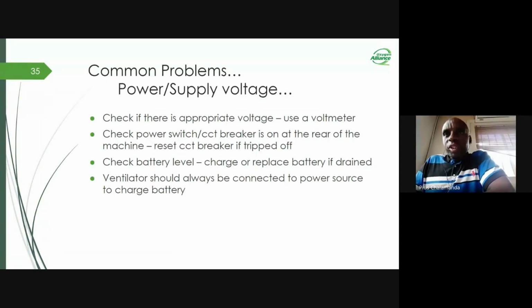You can also check the power switch at the back of the machine, or a circuit breaker at the back of the machine. You can switch it on if it was off, or if the circuit breaker was tripped, you can reset it. You may also check the battery level. If it is low, then you may recharge, or if the battery is drained, then you can replace the battery. The battery is inserted for the purposes of backup, so that if you don't have grid power, the battery can take over to run the machine for several hours, depending on the power available in the battery. Ventilators should always be connected to power so that it continues charging the battery.